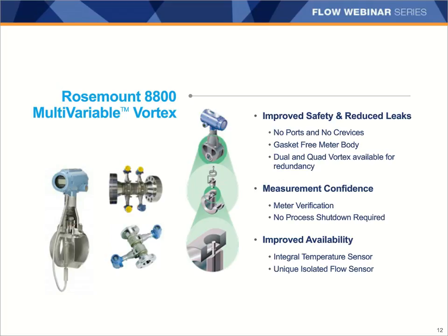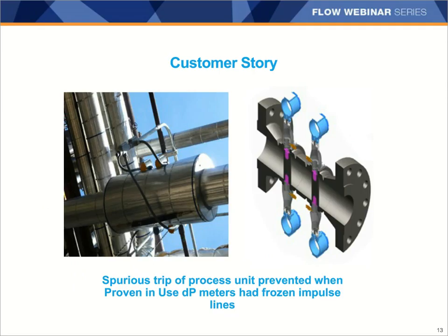I'd actually like to share a story with you about a customer that used a quad vortex for their safety application. So this customer needed a 2 out of 3 voting for a safety instrumented system and required a 4th flow meter for regulatory flow control. A safety instrumented system was installed for personnel protection to almost eliminate the risk of 2-phase backflow from the reactors back to the feed system. 2 out of 3 voting logic greatly reduces spurious trip risk and provides robust SIS coverage. In addition, the 2 out of 3 configuration greatly simplifies online critical alarm testing.